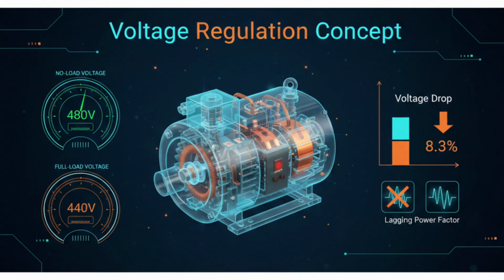You can also see icons representing different power factors. Lagging power factor loads such as induction motors produce larger voltage drops, while unity or leading power factor loads result in smaller drops or sometimes even a voltage rise. Marine engineers pay close attention to this behavior because excessive voltage fluctuation can damage sensitive electronics and motors on board.